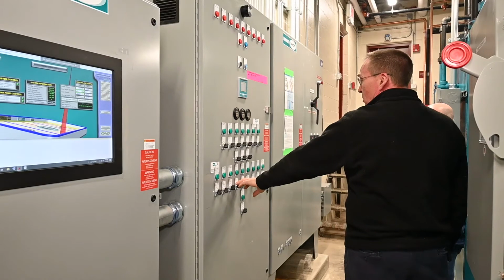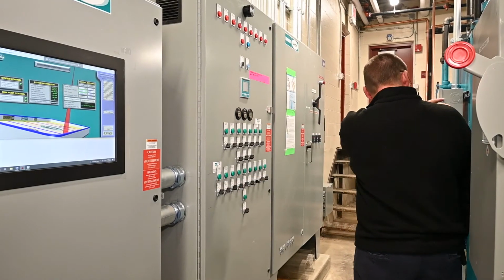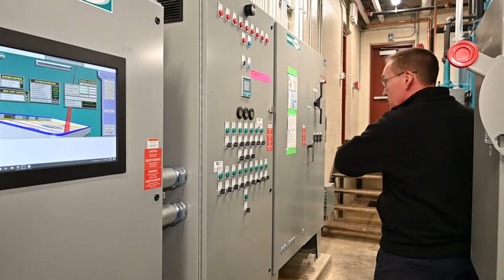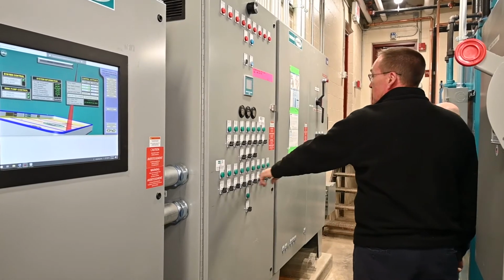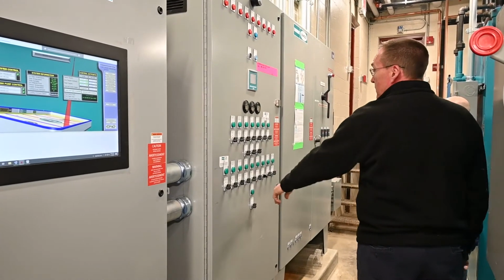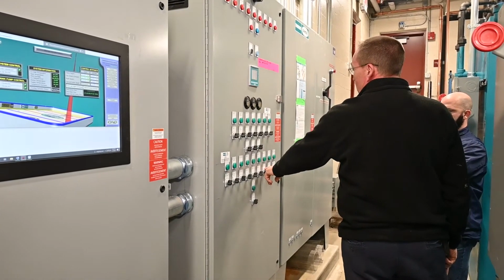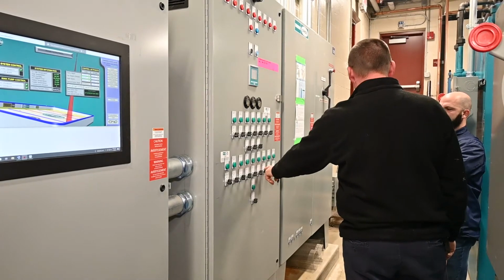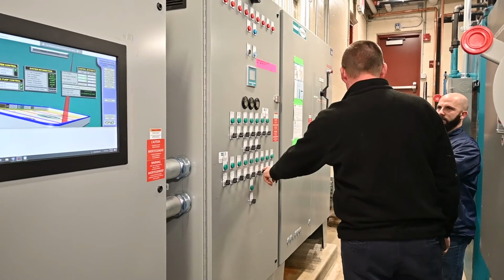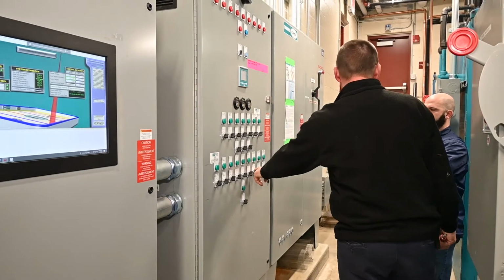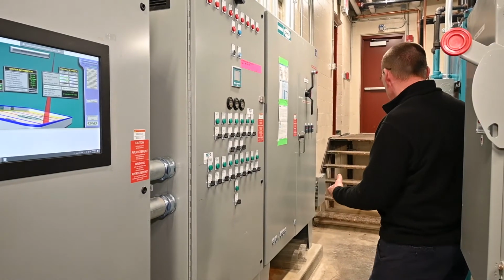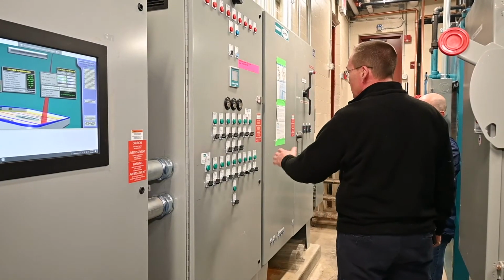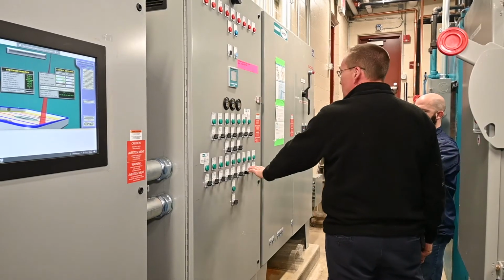GP1, cold glycol pump 1, is the cold pump, the vertical pump mounted to the backside of chiller 1. Number 2 and number 3 over here. Cooling tower water heater, that's not in play here. There is not a heater in that tower because we drain back to the sump tank. The original design had an integral sump. In this design, when this panel was built, it's just there. There's nothing wired to it.